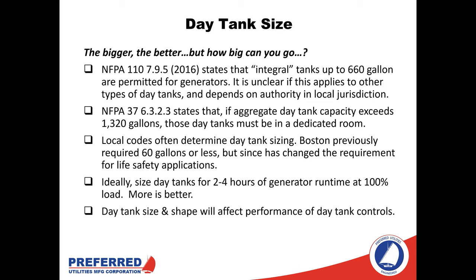Moving on to day tank sizing — this is the tank located at the generator, sometimes called a belly tank depending on its size, location, and configuration. For the amount of fuel this tank needs to store, it's very important because this is the tank the generator has immediate access to. If there is a failure in the transfer system or problem with piping and valving in the rest of the system, this is the amount of fuel the generator can immediately use. We want to give ourselves time to address problems, so for life safety or mission-critical applications, we look at two to four hours of generator runtime from the day tank.